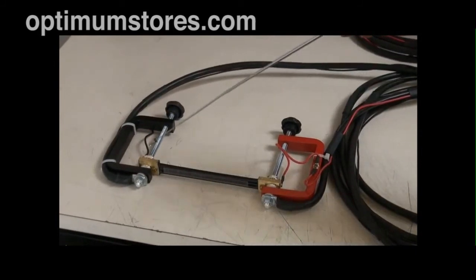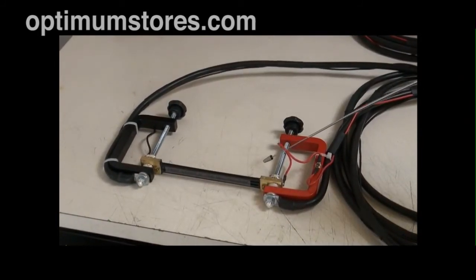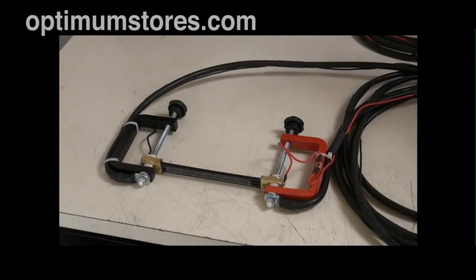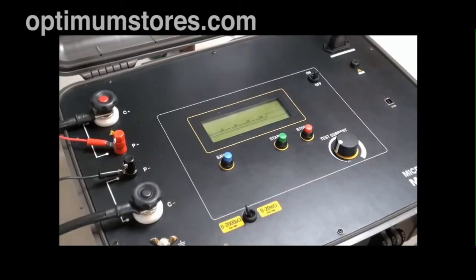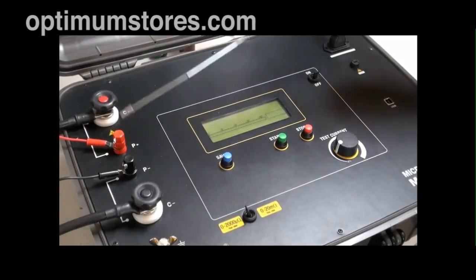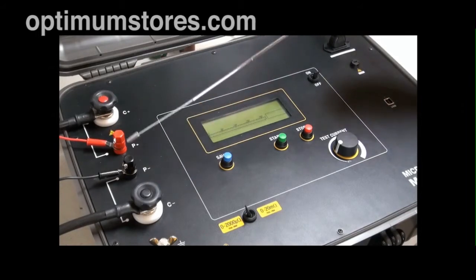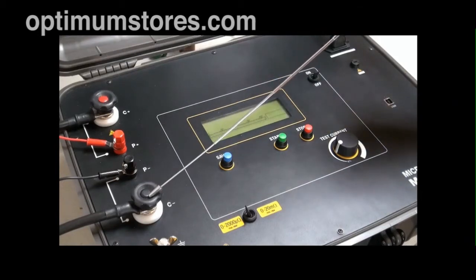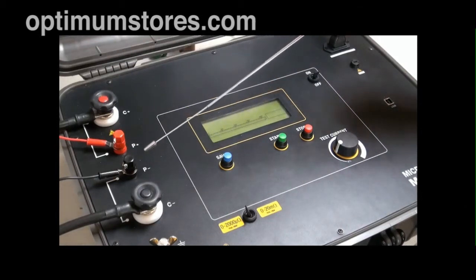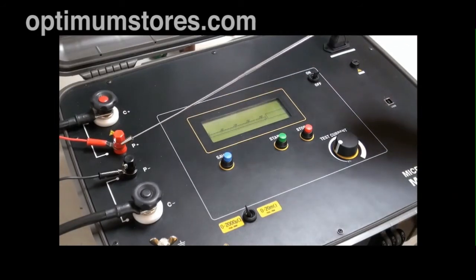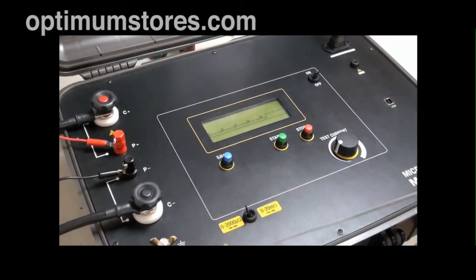Now what we have here is a 1 milliohm test standard that we're going to use to indicate on the device and guarantee that it is functioning properly. We have our test leads coming back and being connected to our test device. First, what we do is make sure we have all our connections properly. These are all color coded. We know that we have our injection terminal, our return path, and then our two potential terminals hooked up properly. Again, they're color coded to make it easy and ergonomic. In this case we're not using the grounding. Then we go to our on switch and turn the device on.